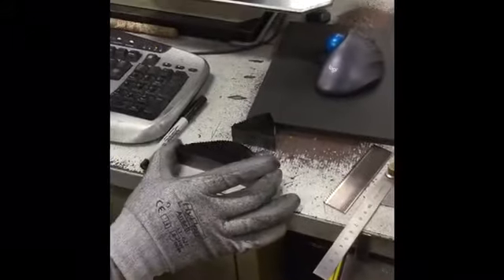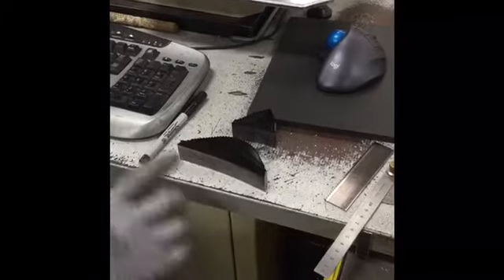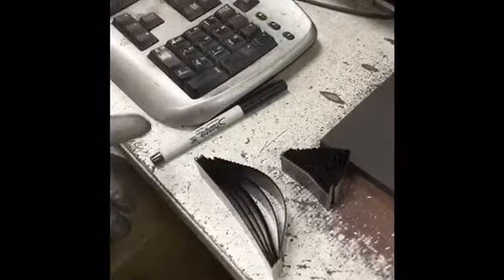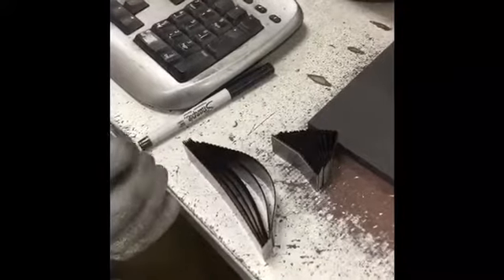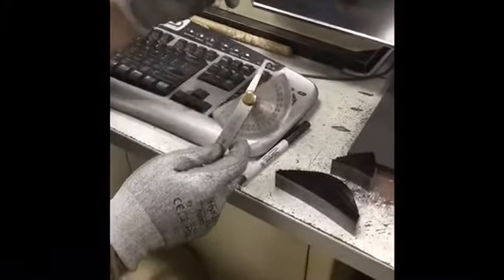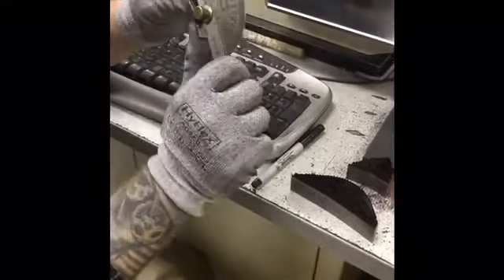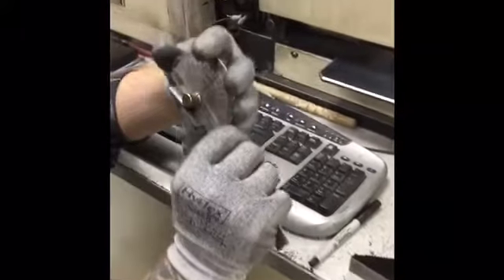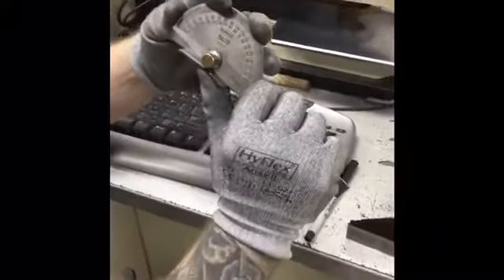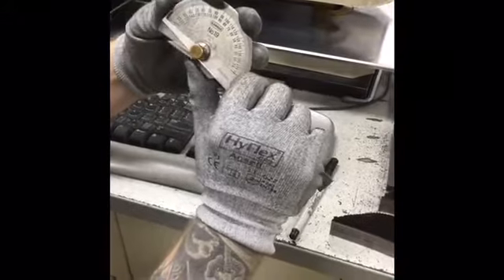I've separated the pieces here to show you that up to 10 degrees, you're going to get pieces with 10 hits on them. Once you get to 15 degrees, you're going to get smaller pieces like this, because 15 degrees is a lot more visible and doesn't need 10 hits, just 1 bend. So for 15 degrees, you just measure it outright as it is. Whatever the protractor says is whatever you put in.